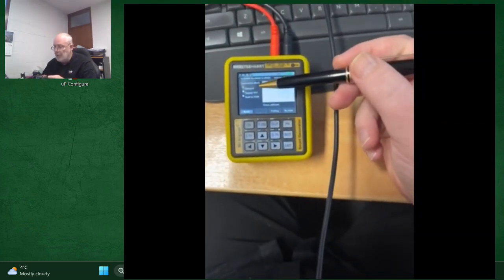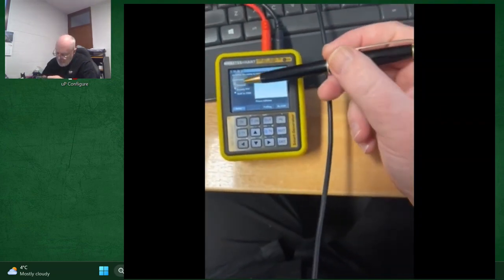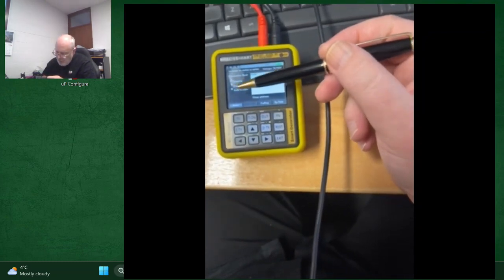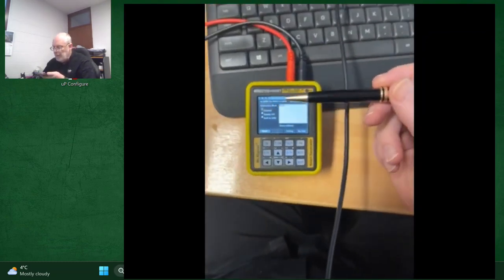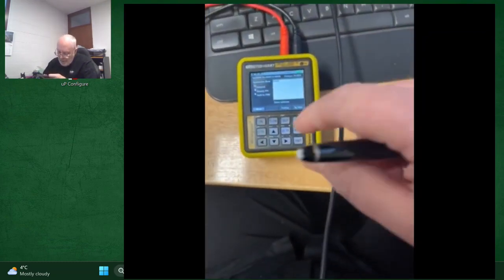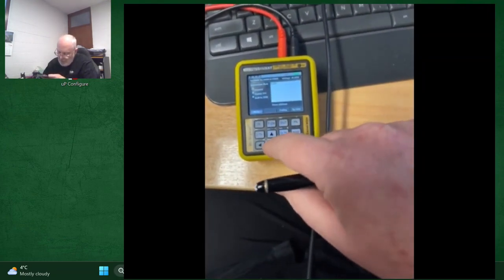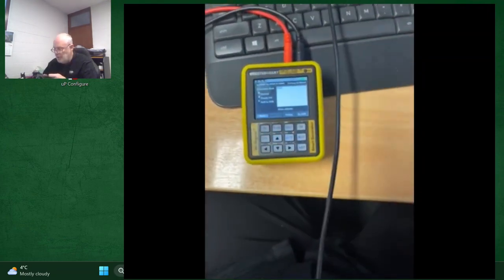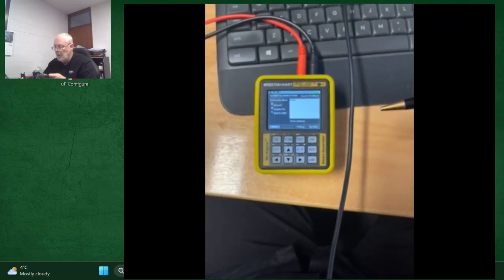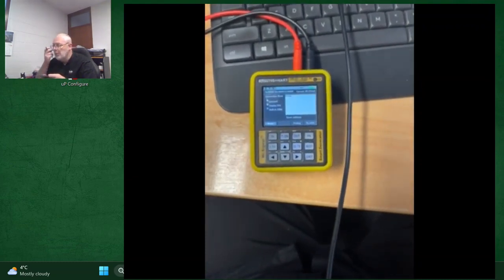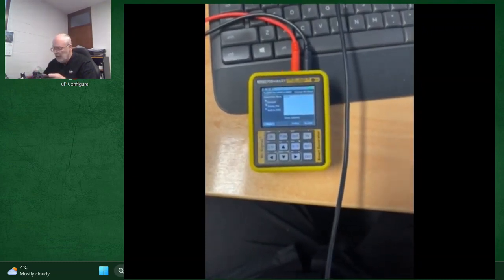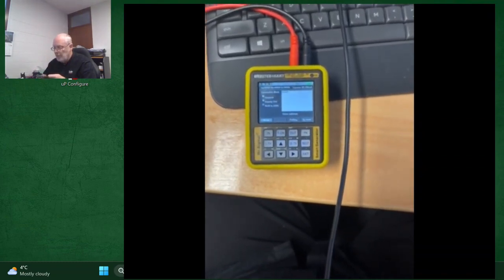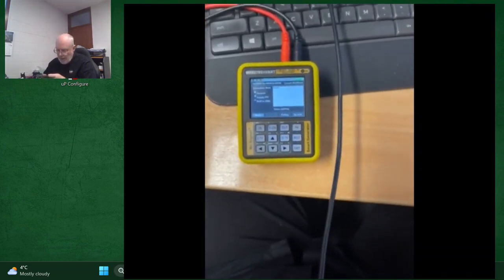Now we have three choices on the left. We have general supply 24 volt or built in 270 ohm. I'm still working my way through the other two, but we know that for any HART communication that we need to have a 270 or 250 ohm resistor to create a voltage drop across that resistor to activate the, or to give the HART something to read.